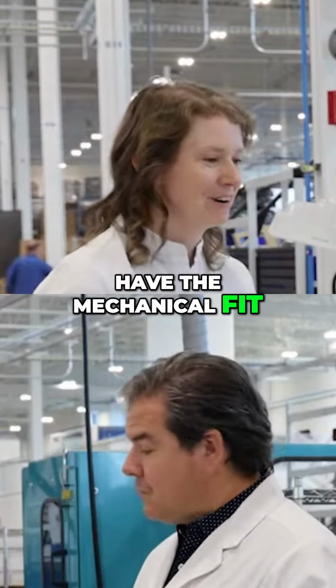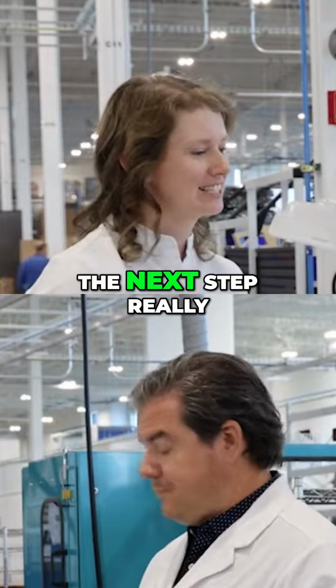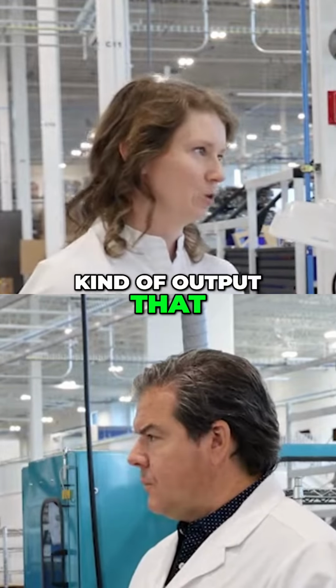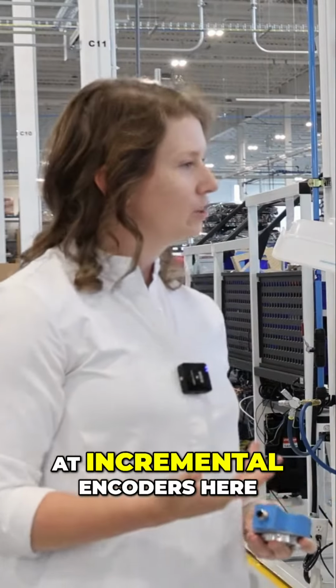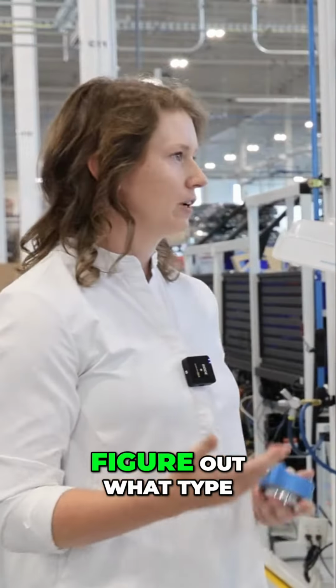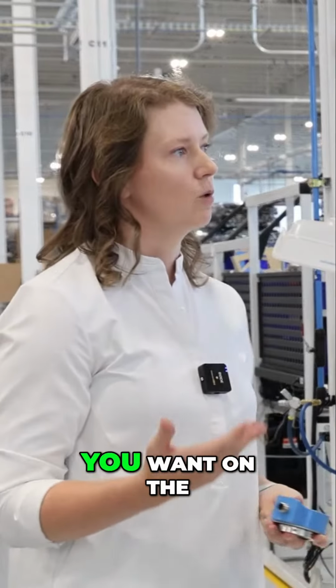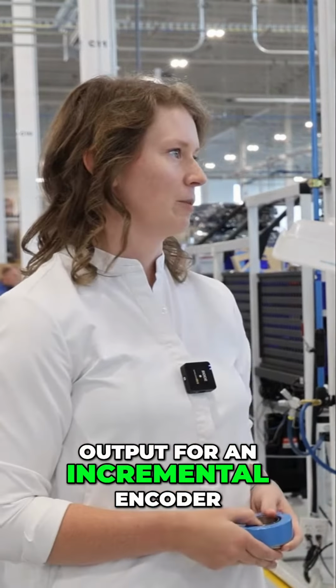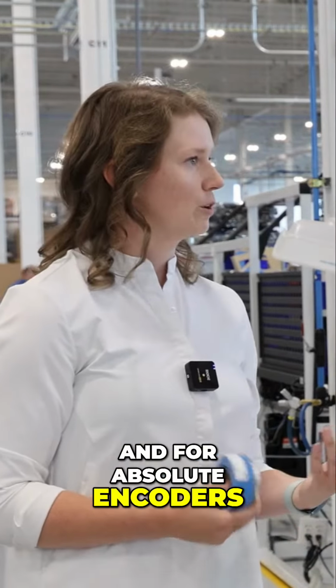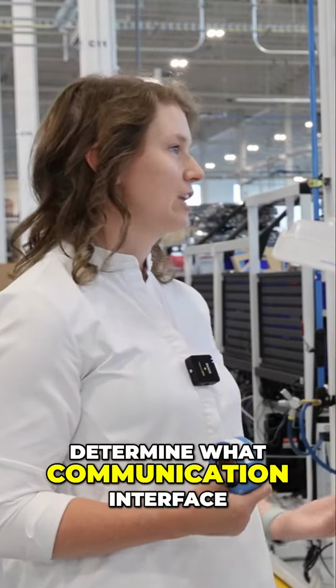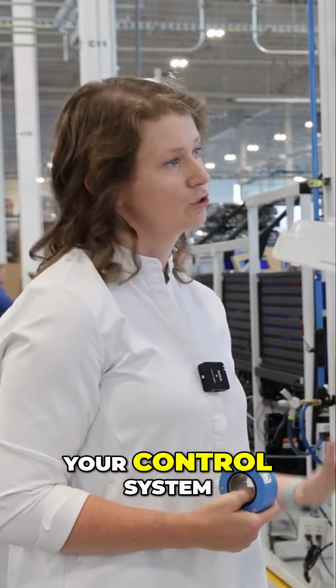Okay. And then once you have the mechanical fit fairly determined, the next step really is to determine what kind of output you want. So if you're looking at incremental encoders, here you typically want to figure out what type of voltage amplitude you want on the output. And for absolute encoders, you're really trying to determine what communication interface you need for your control system.